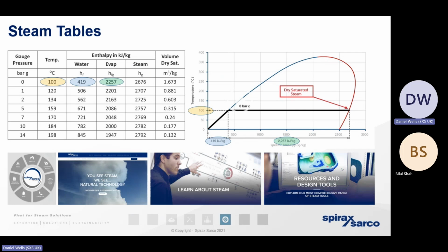But look what happens here. When we've reduced the pressure 1,000 meters away at the heat exchanger, as a means of allowing the steam to move and as a means of controlling the temperature, there's actually more useful energy present within it. So the enthalpy of evaporation, that's the energy we need to put into that boiling water to make it change state, is also the energy that is capable of moving across the heat exchanger to heat the process up. So if you've got steam tables at home, or that you refer to for your college, I'd probably put a line through the enthalpy of evaporation. Call it the useful heat energy.